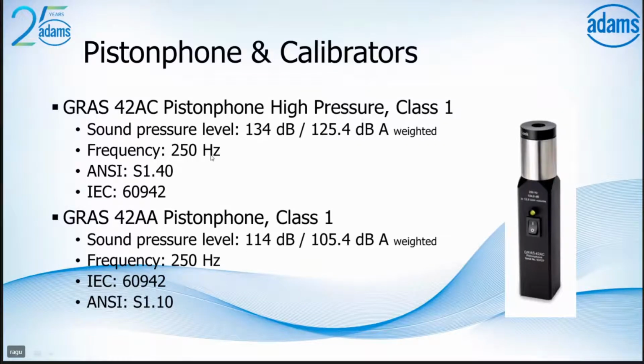So if you have microphones with a measuring range up to 180 dB, it is recommended that you use this because you'll be able to calibrate your microphone at a higher level. 42AA is the standard pistonphone, 114 dB. This is the common specification that is available in the market. So if your microphones are the standard general purpose range of 120 dB or 140 dB, you can go for the 42AA. If it's more than that, it is recommended that you go for the 42AC.